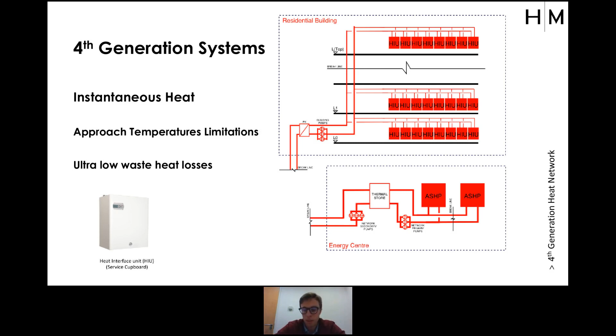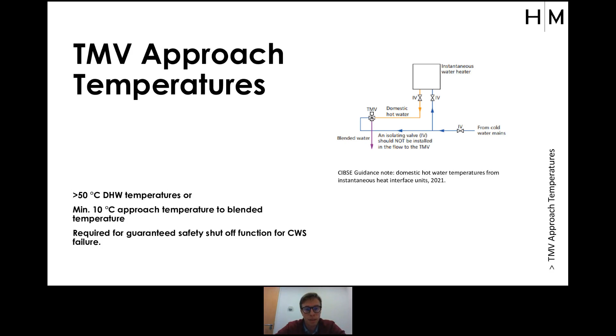The air source heat pump side operating at these high temperatures, obviously the COPs drop, and I'll go on to the limitation in the minimum operating temperatures, which is quite well constructed in a new CIBSE guide. I would also recommend looking at it. It's been recently issued this year, putting an industry point of view on domestic water temperatures, which previously there was a lot of discussion on. So thermostatic mixing valves and so on, protecting your users from scalding temperatures, they require a minimum approach temperature to work safely. So often that's about 5 degrees, 10 degrees temperature. I was thinking about HIU approach temperatures then, but that needs to be considered. So that's really defining your minimum network temperatures. And then the other consideration on your network is heat exchangers, which can be a big penalty in terms of operating efficiently for your central plant. So it's worth considering those.